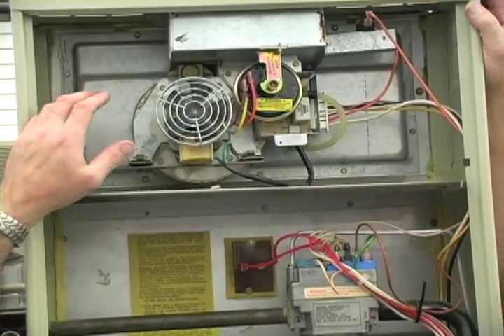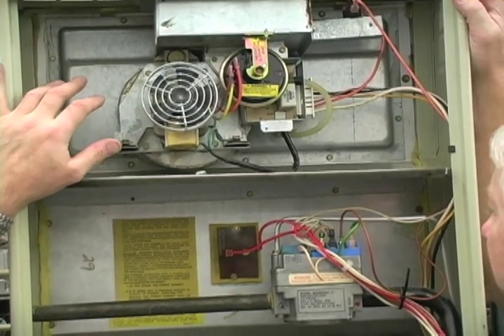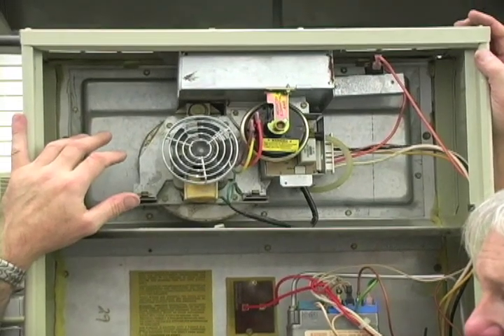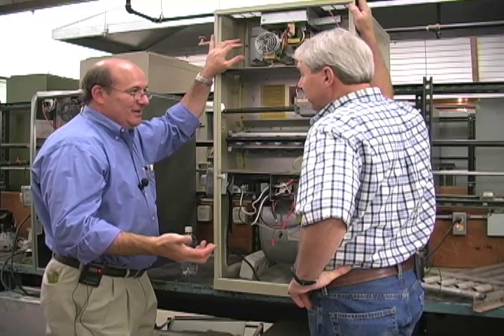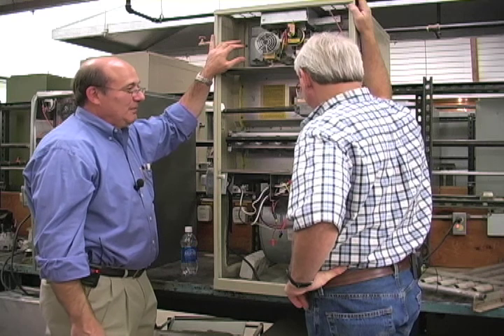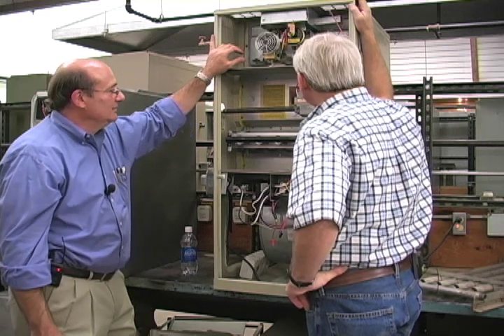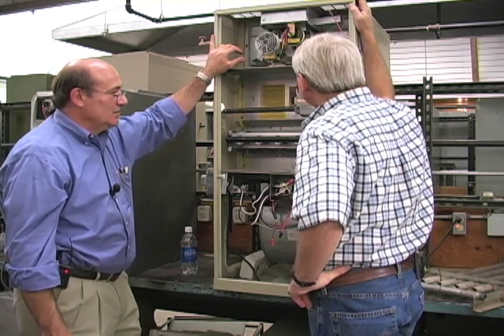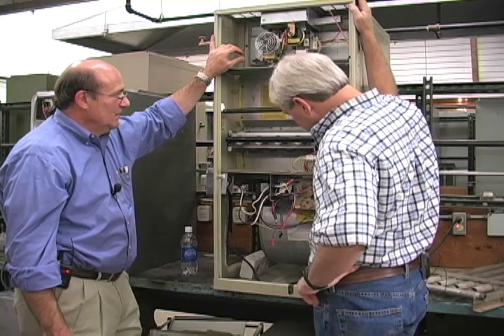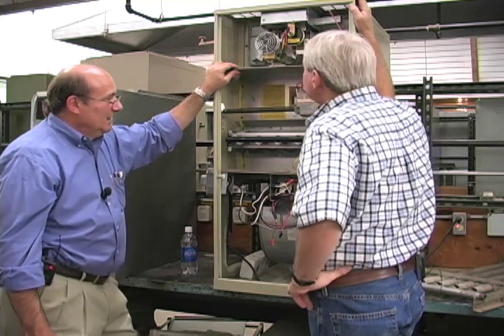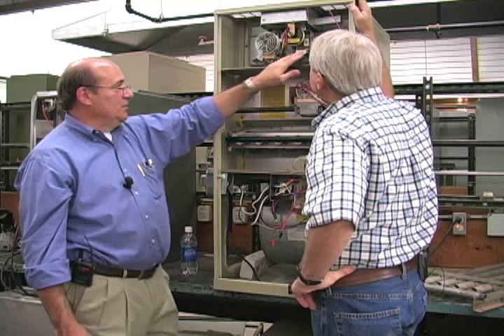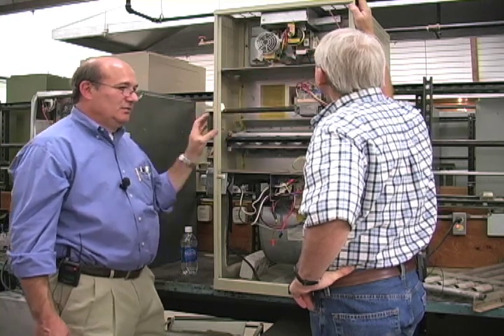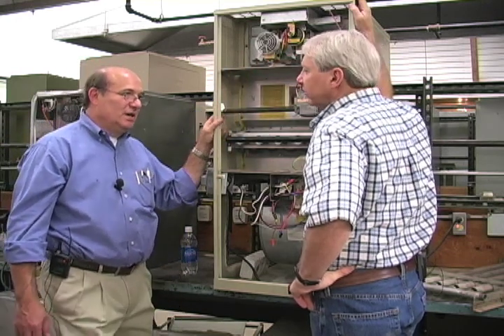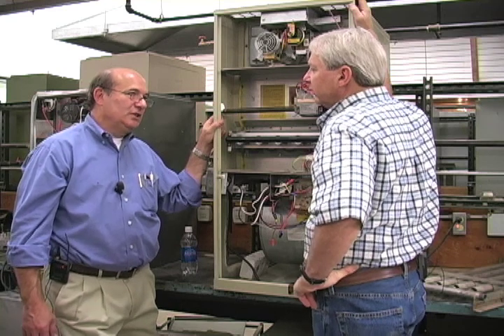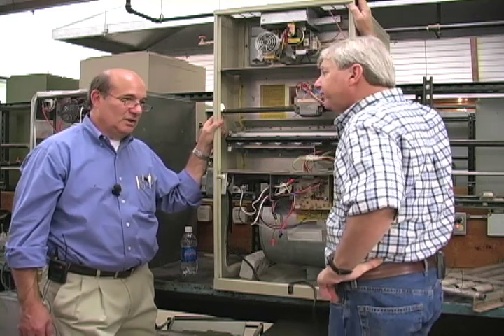You could actually experience problems with your system, like a plugged up vent, but the centrifugal switch might still make. So it'll still be spinning. Yeah. Pressure switch is a better, safer alternative, and we'll see those on all of the newer systems. One other final aside: these pressure switches, we're dealing with very, very low pressures. Inches water column, maybe a couple of hundredths of an inch of water pressure, water gauge pressure.